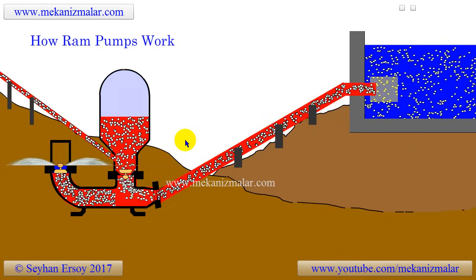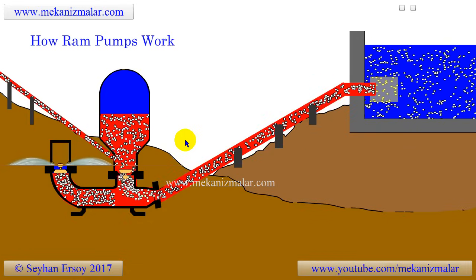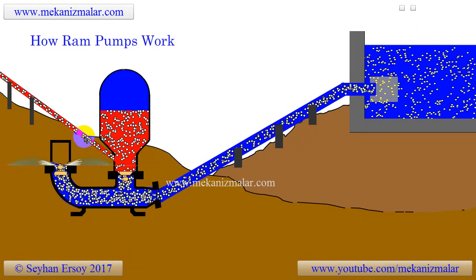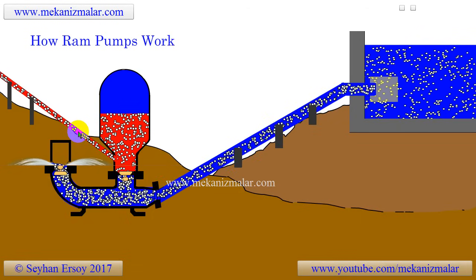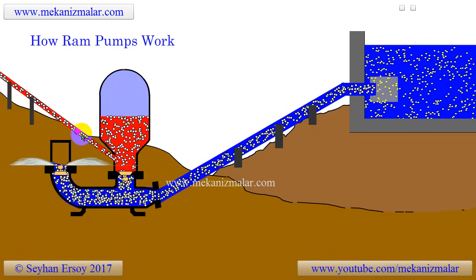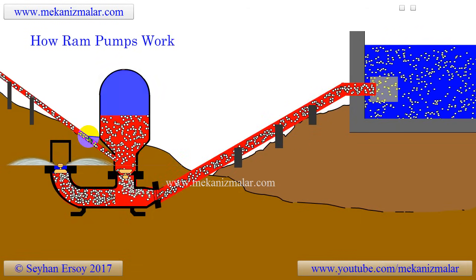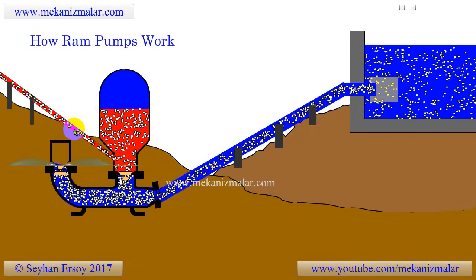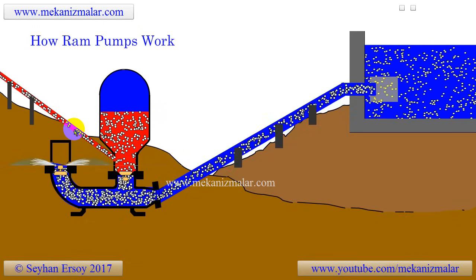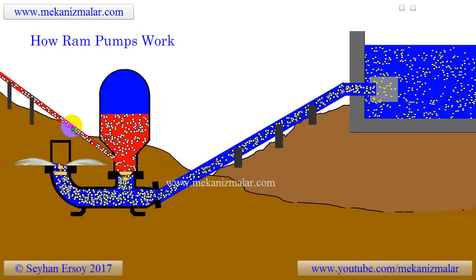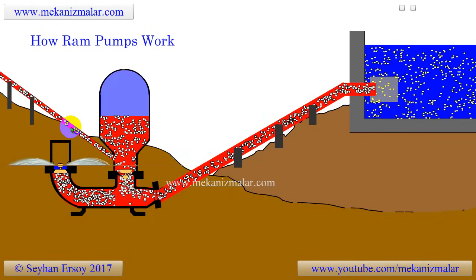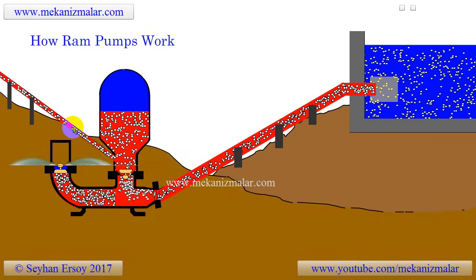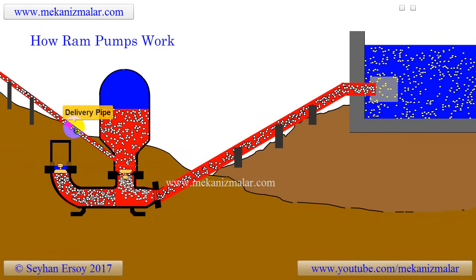However, the water continues to flow through the delivery pipe, and this is due to the pressure of trapped air inside the accumulator. The accumulator acts just like a flywheel, regulating the water flow rate through the delivery pipe and absorbing pressure spikes from the system.